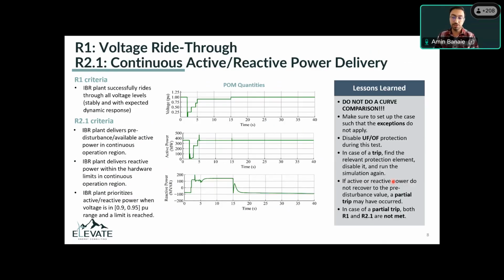Now jumping into each requirement and things that we have learned by running dynamic simulation on our test setups. So we have designed for PRC-029 around 8 to 10 simulation cases for requirements R1 and R2.1. How we do it is that we apply the LVRT and HVRT curves of PRC-029 in tables 1 and 2 in attachment 1 at the POM of the plant. And then we look at active and reactive powers at the POM.